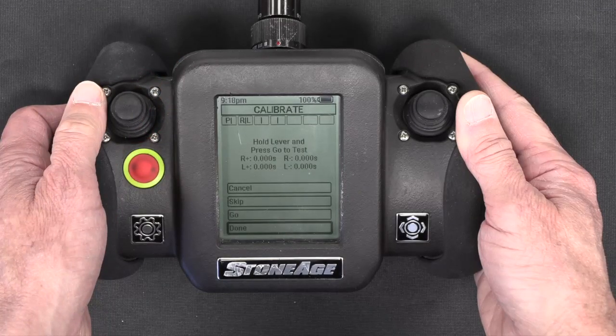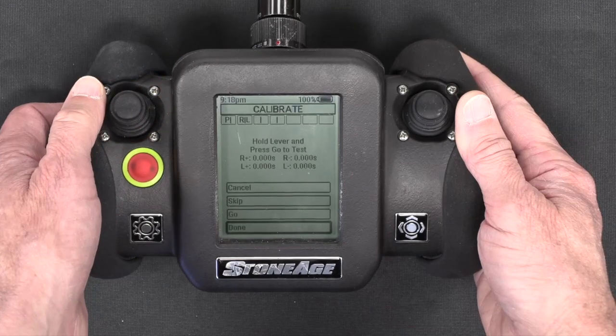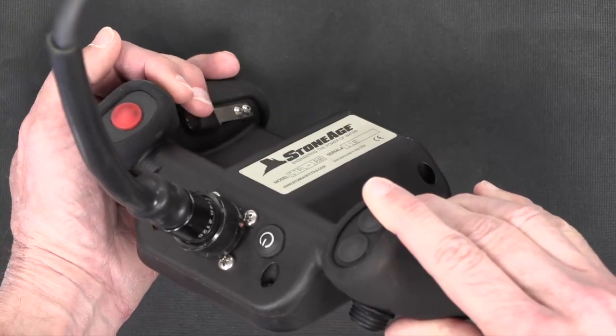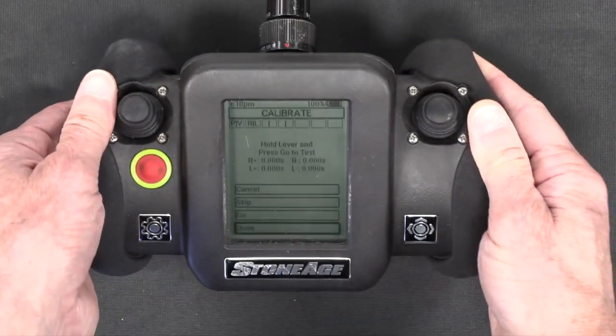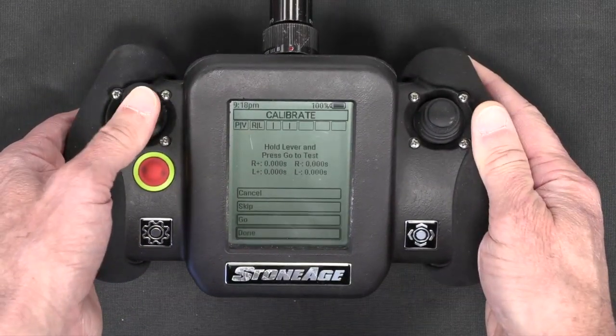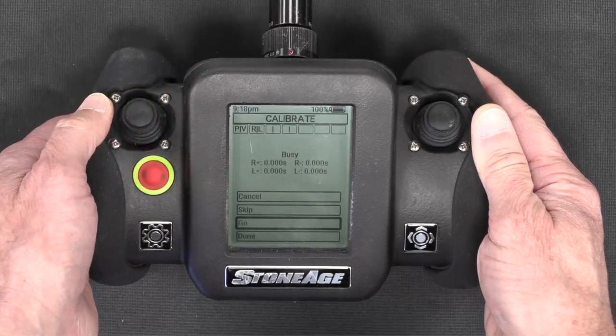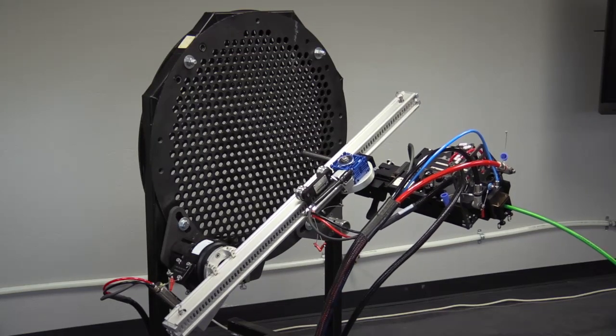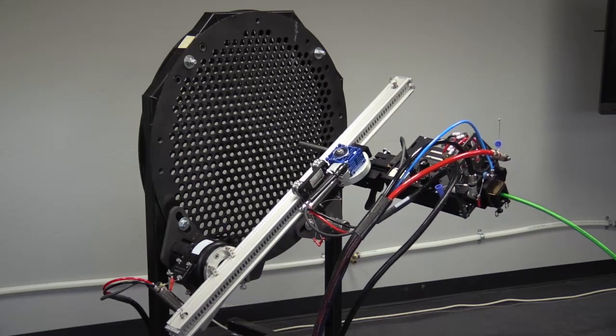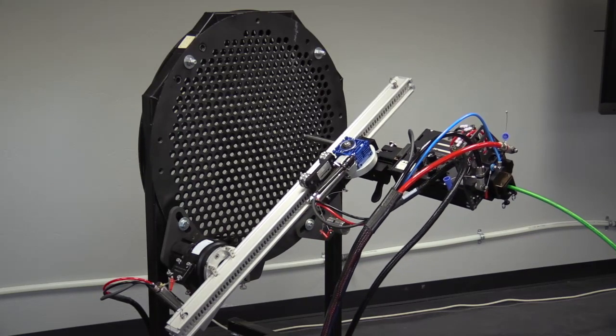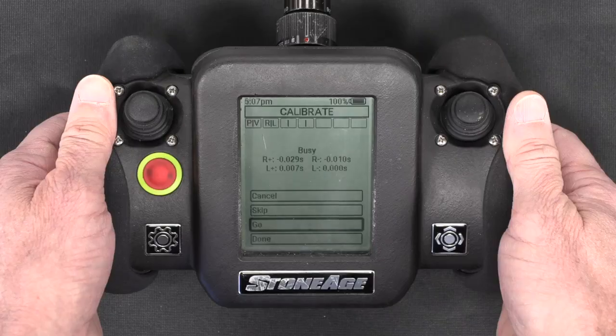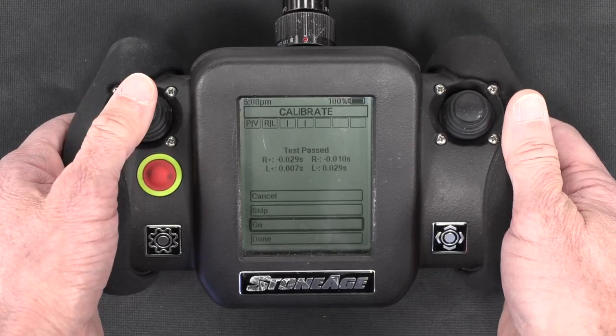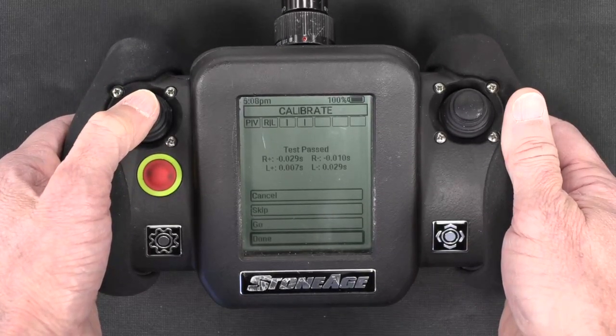The calibration starts off the same as it does for the lightweight positioner. You depress the actuation lever on the back of the controller and click the Go button. The compass positioner will make 4 different moves to measure the mechanical characteristics of the motors. Upon successful completion, you will see that the test is passed and you can click Done to continue.